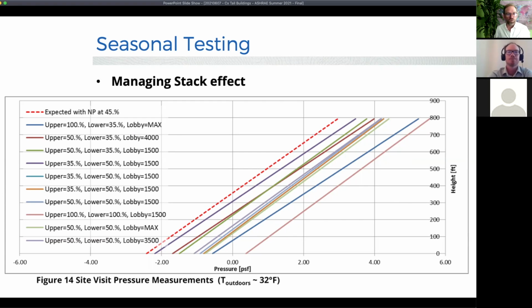However, it really wasn't working because in this case, the engineer, the designer of the system, had felt that in winter I need to pressurize my lobby 100% to manage the stack effect. But in this case, they were actually making the issue worse. They were pumping the elevators full of air because it had nowhere to go, there was no exhaust there.